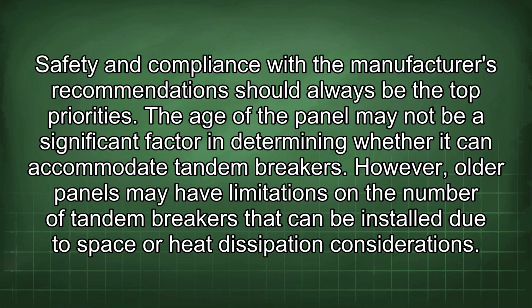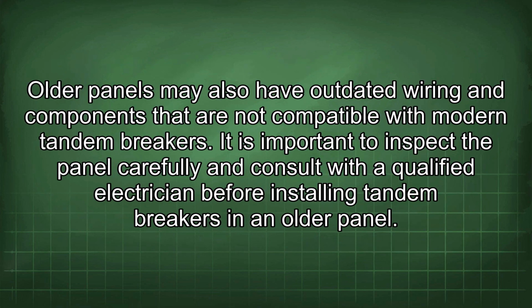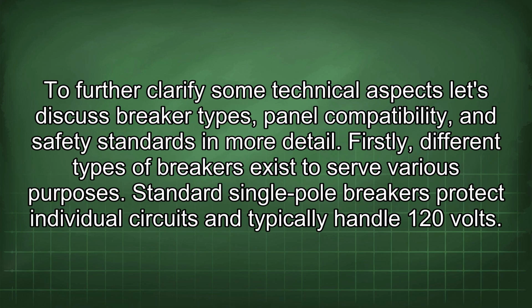The age of the panel may not be a significant factor in determining whether it can accommodate tandem breakers. However, older panels may have limitations on the number of tandem breakers that can be installed due to space or heat dissipation considerations. Older panels may also have outdated wiring and components that are not compatible with modern tandem breakers. It is important to inspect the panel carefully and consult with a qualified electrician before installing tandem breakers in an older panel. To further clarify some technical aspects, let's discuss breaker types, panel compatibility, and safety standards in more detail.